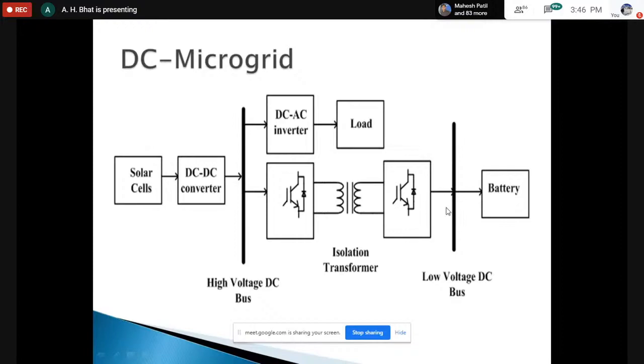This battery will start delivering power to the low voltage DC bus, and from this low voltage DC bus, power will flow from this converter to that converter, because it is a bidirectional DC to DC converter. Now power will flow from the low voltage DC bus to the high voltage DC bus, and since this high voltage DC bus is feeding the load, whatever demand is there will be fed from this storage.